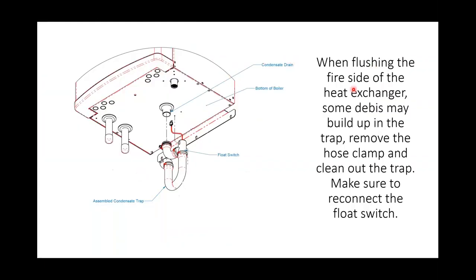When we're flushing out the fire side of the heat exchanger, we may get some debris that's going to form inside of our condensate trap. With all the water we're pushing through, it should flush it out of the trap. We want to make sure that the drain's clear and it's free running. But if the debris gets trapped in there and it's not leaving, that's when we would disconnect the hose clamp off the base and the float switch harness from the boiler, take it out, and then clean the trap and put it all back together.